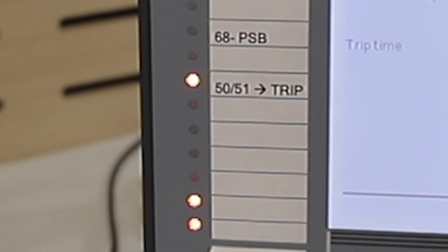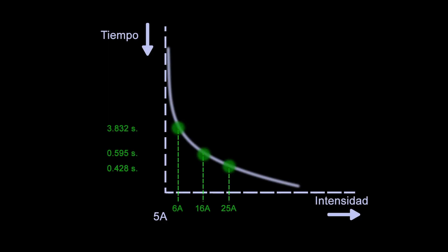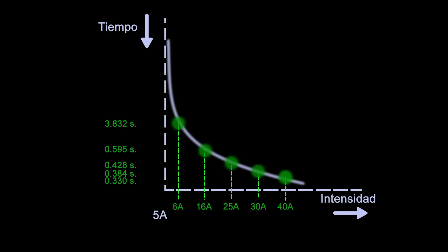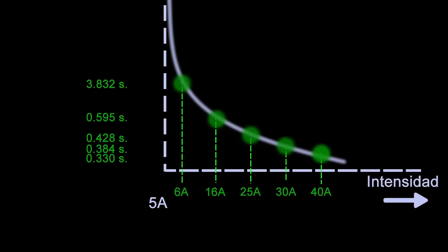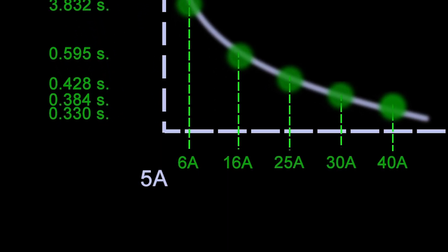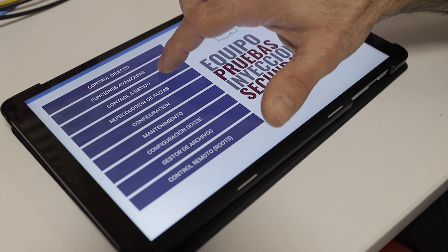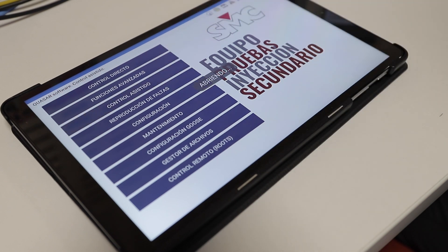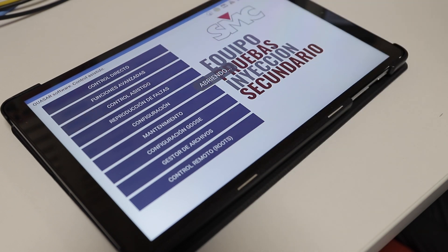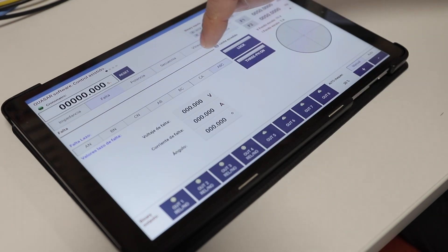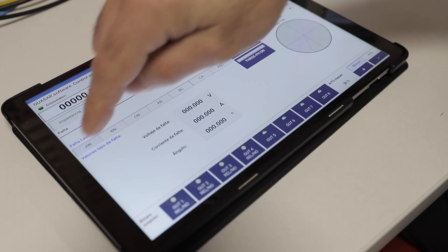In this tutorial, we will measure the relay's operation time with a few different current values, starting with one at the very beginning of the overcurrent protection zone. The fault function in the Quasar's assisted testing mode provides a quick, intuitive way to do this.